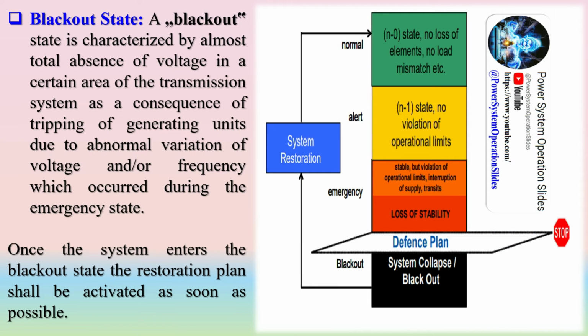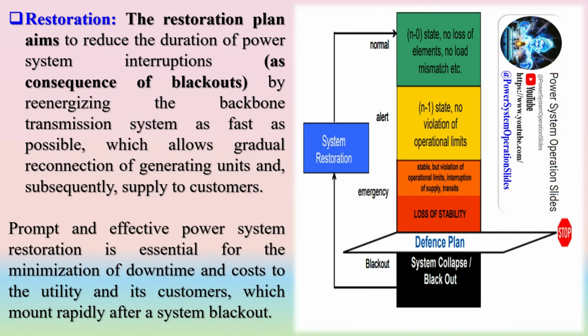Typically, the system reaches this state after a N-1 contingency. This state requires application of remedial actions without any delay in order to come back to the secure state, i.e. to comply with the N-1 rule. Emergency state: as a consequence of contingencies beyond N-1, extreme or unforeseen contingencies, the individual variables that describe the overall system state could violate admissible operational limits and hence the system is considered to be in an emergency state, a disturbed state. A system being in an emergency state might not be able to fulfill its function with respect to consumer supply and power transits, but is not blacked out. However, there is the risk of system collapse mainly due to the loss of stability. Therefore, relevant actions must be taken immediately to bring back the system into acceptable conditions.